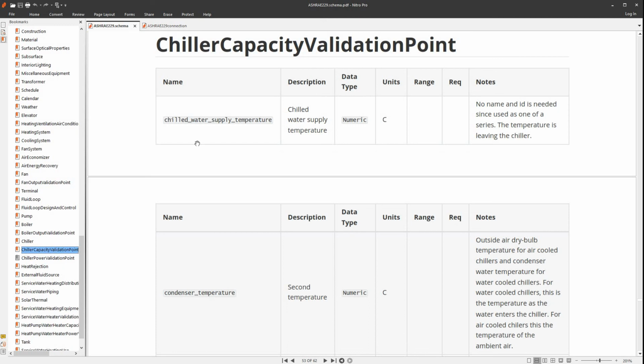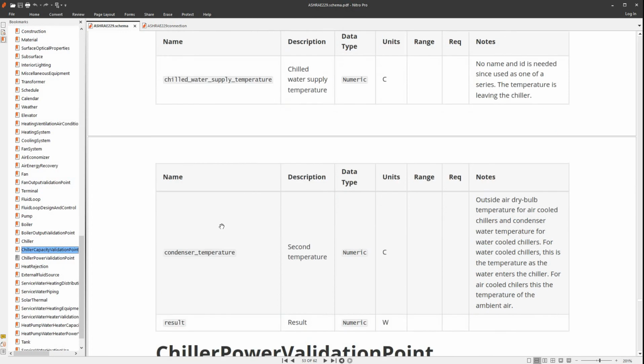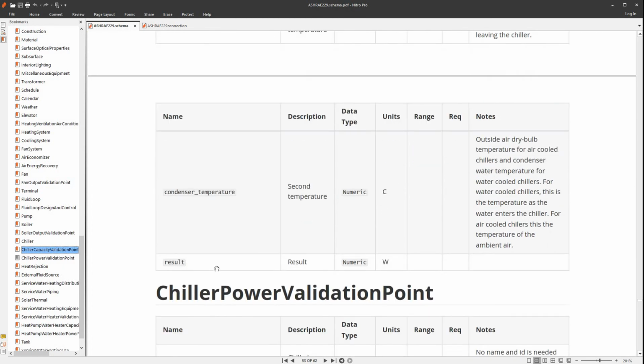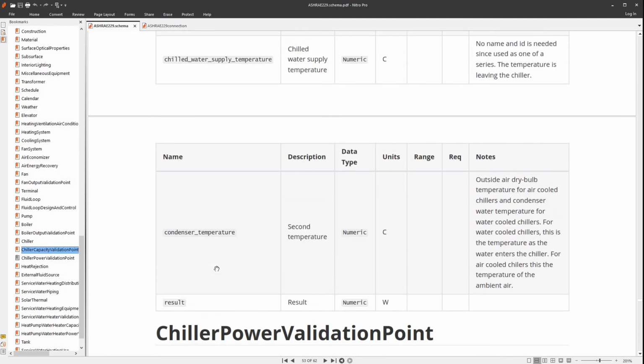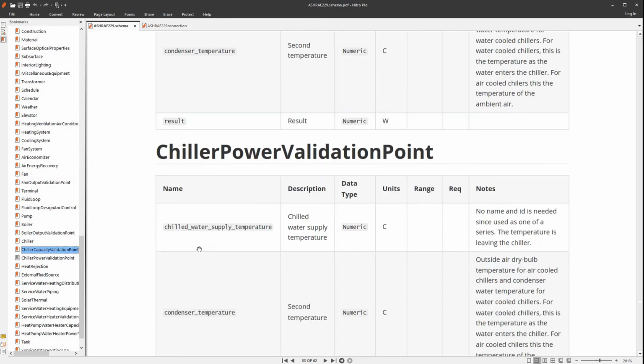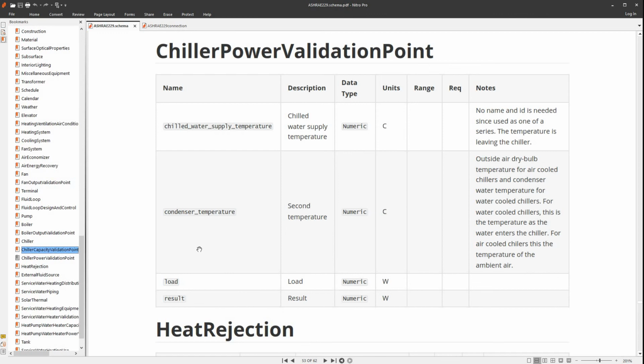So for the capacity validation curve, there's the chilled water supply temperature and condenser temperature, as well as the capacity itself, or result. Now for air-cooled chillers, the condenser temperature would be the outside dry bulb temperature. Likewise, for the power validation points, they have similar inputs, but they also add the word load. So at different load levels, there'd be different results. So basically, between these two lists of validation points, you'd be able to completely describe points in both the capacity and efficiency curves for chillers.